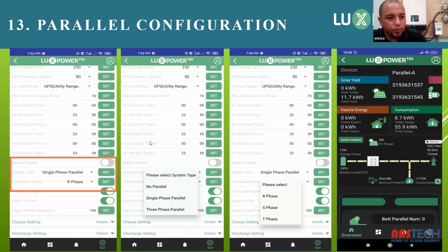Setting up your parallel for your inverters, you would go online onto your app. You would go to the single phase parallel. If it's for single phase, they will all be on the R phase. If it's for a 3-phase parallel, you would have to set them accordingly. The output phase of the inverter has to be linked to the input phase of the inverter. So if you have RST on 3 inverters, the output needs to be congruent to the input of those inverters. So if there is a mistake on the supplier side, where 2 phases are actually 1 phase, the inverter will let you know that there are actually 2 phases that are 1 phase being given from the supplier.